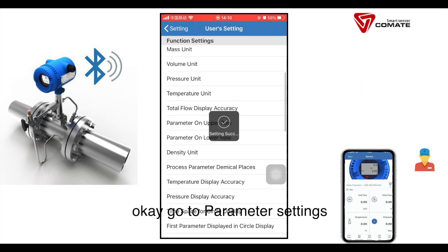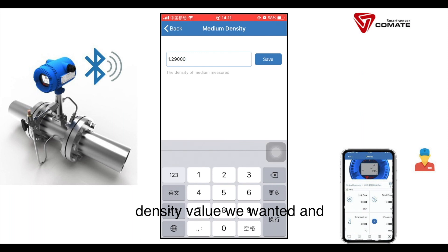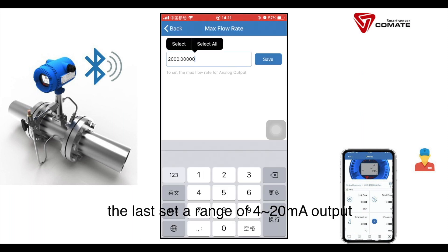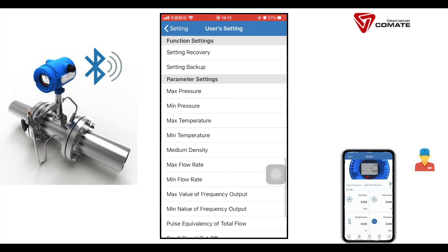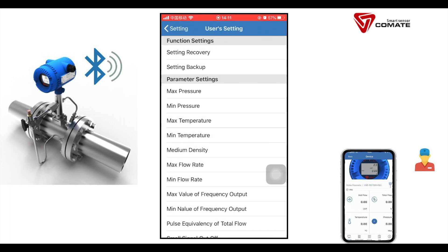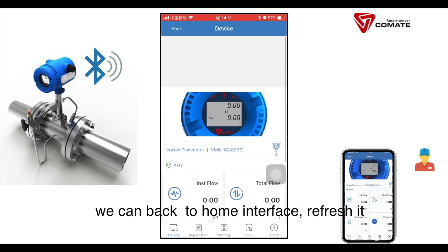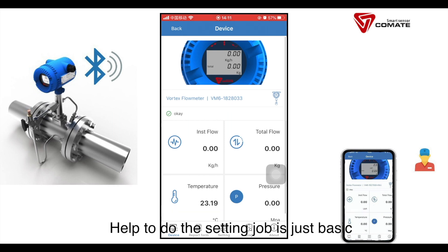Go to parameter settings. For medium density, we input the value we want. Then, set the range of the 4 to 20 mA output. After all settings are finished, we go back to the home interface, refresh it, and you can see the mass unit has been changed.